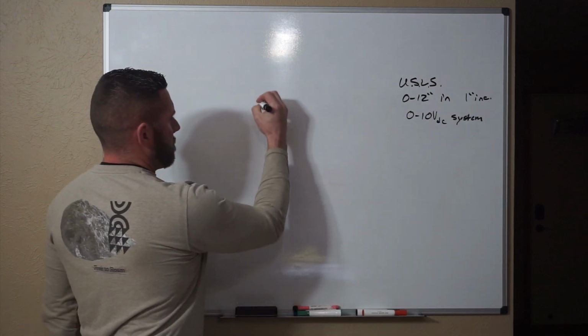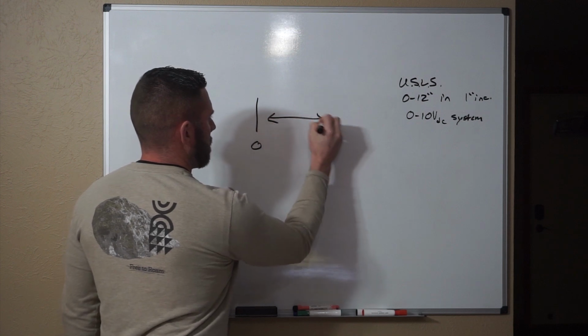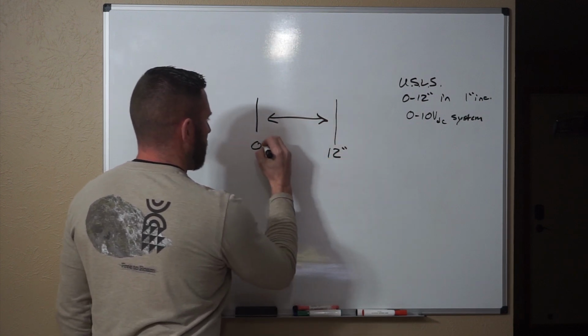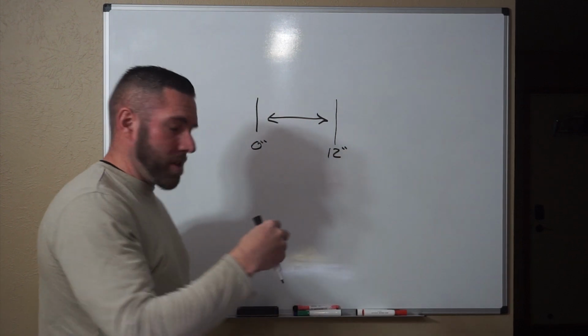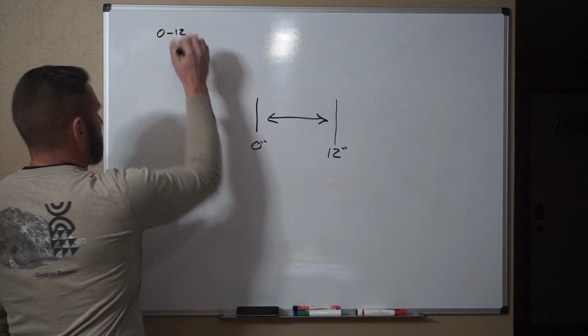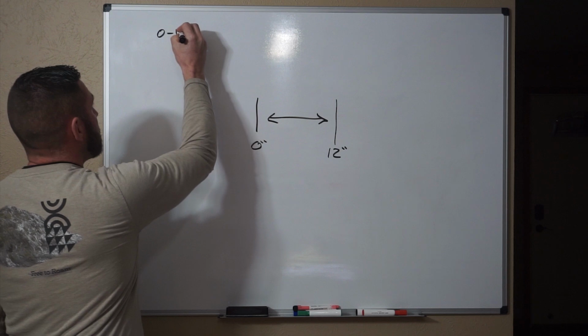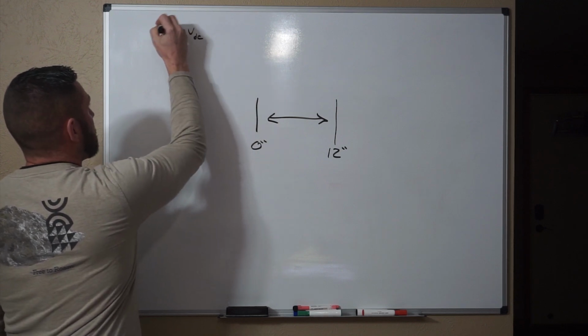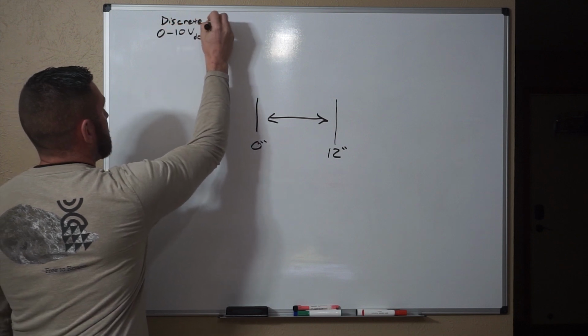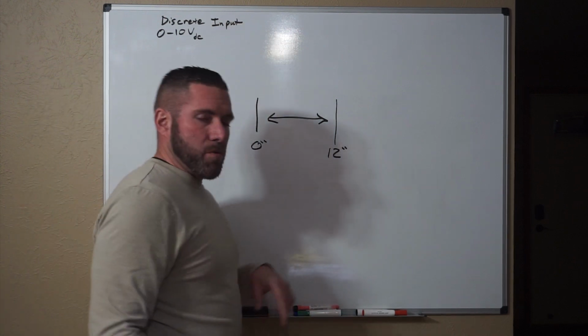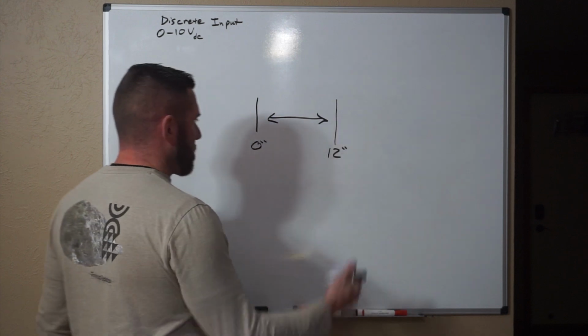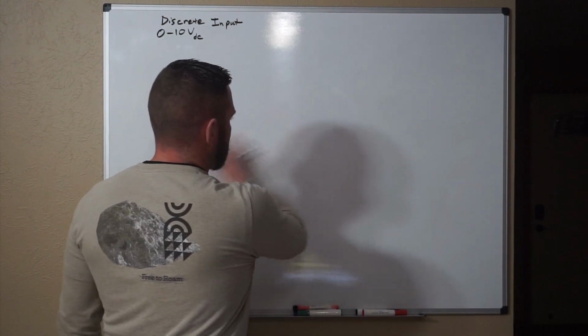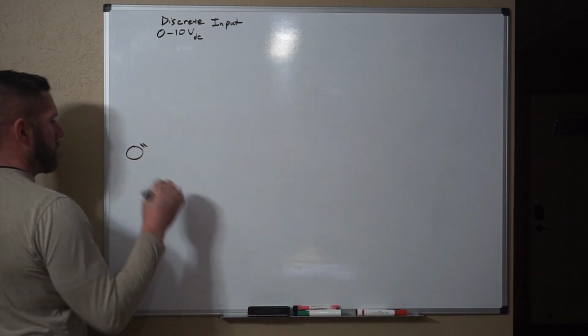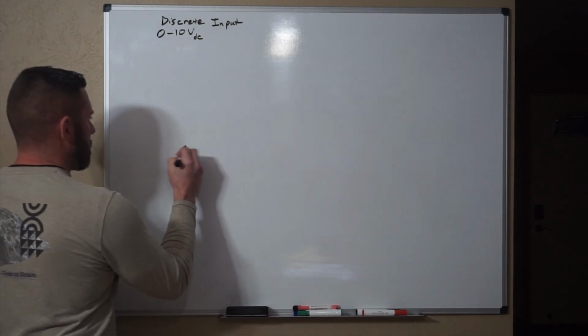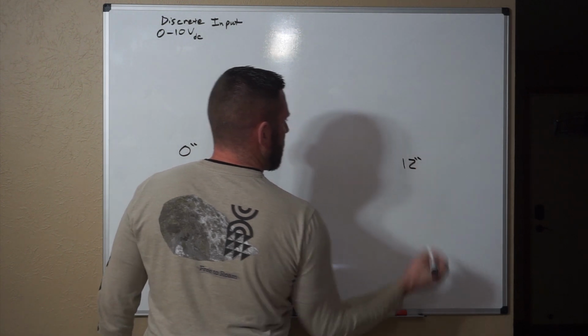When we pick this out, we want to measure from 0 to 12 inches. So when we pick this ultrasonic level sensor, and we know that the module on the other end is a 0 to 10 volt DC discrete input. Okay, so we're going to have high highs, low lows, highs and lows, alarms. So let's put some alarms in here too. Let's start to build what our sensor actually needs to be. We're going to move this over a little bit. So that's our lowest, and that's our highest alarm.